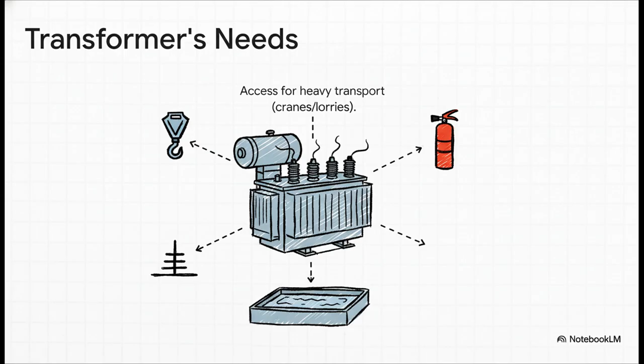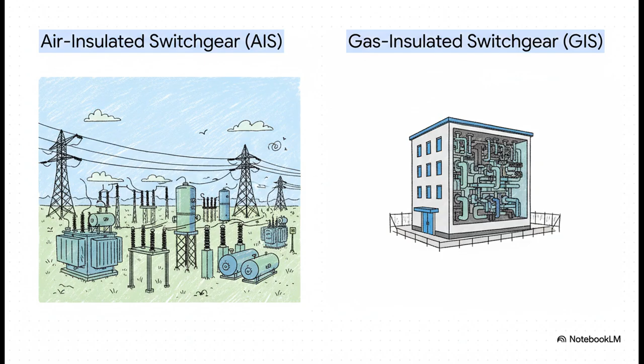All right, on to the traffic cop. There are basically two main ways to build the equipment that directs the flow of power. The traditional way is air-insulated, which is what you're picturing in your head, those big, sprawling outdoor substations. But the more modern, compact version is gas-insulated. Let's focus on this modern approach for a second. Gas-insulated switchgear, or GIS for short, takes all the control parts, the switches, the circuit breakers, and seals them up in a metal tube filled with a special insulating gas.